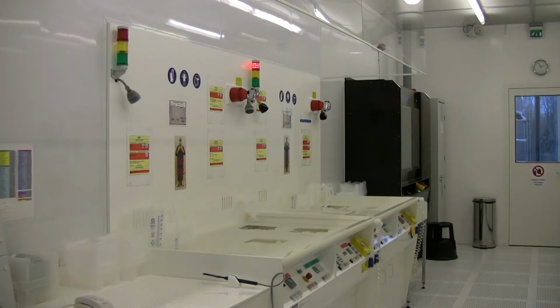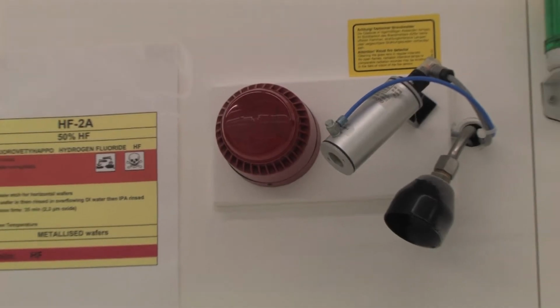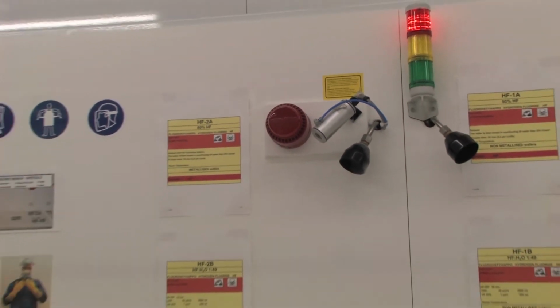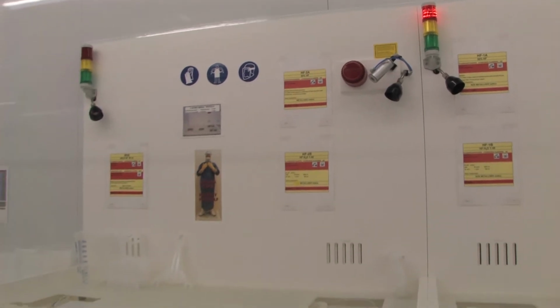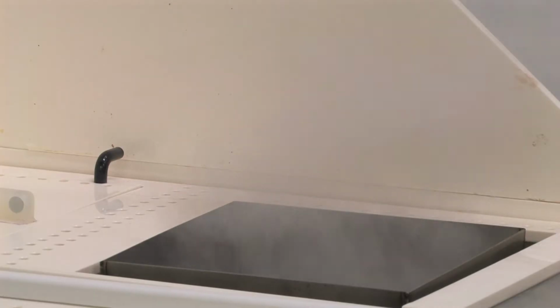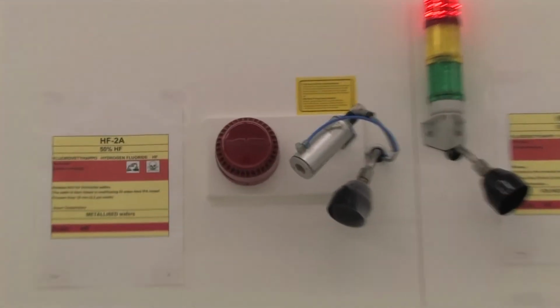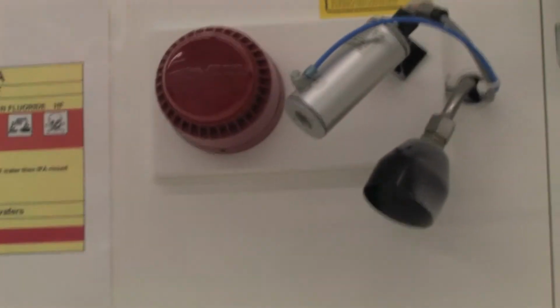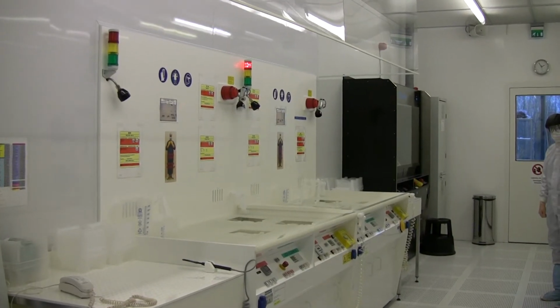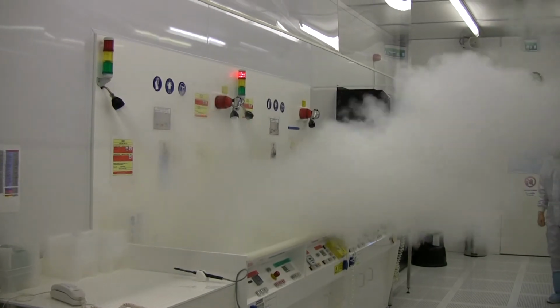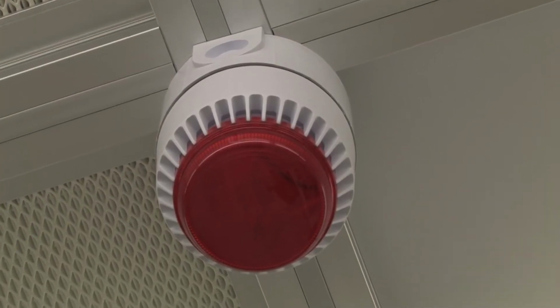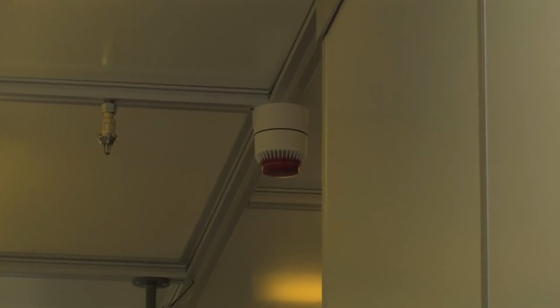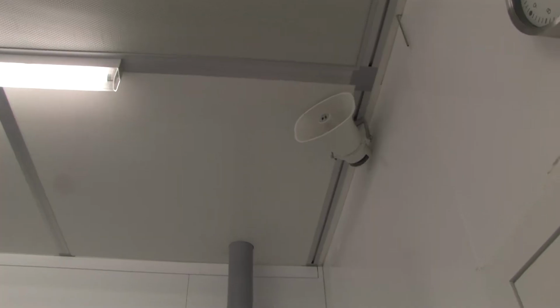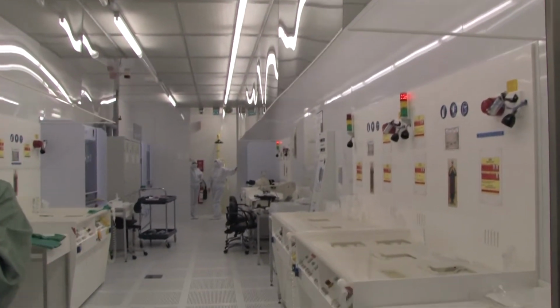Most wet benches and fume hoods in the VTT part of the cleanroom are equipped with flame indicators and automatic carbon dioxide extinguishers. When the system detects flames in a solvent tank, for example, it sets off a sound and light alarm, and after a short delay, carbon dioxide extinguishes the fire. At the same time, a fire alarm is sounded in the cleanroom and sent to the Regional Fire Brigade control. The situation is not dangerous because the carbon dioxide is removed very quickly through the ventilation system.